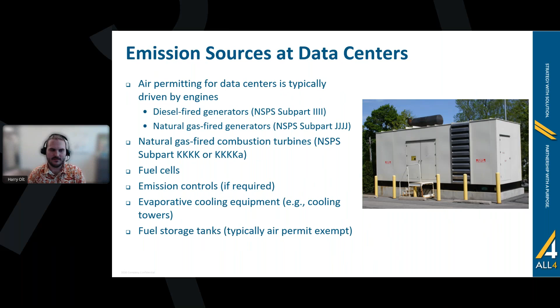Non-emergency generators and fuel cells are also considered for this on-site generation, and they would require air permits as well. If emissions controls are required for your site, those would also need to be in the air permit to take credit for emissions reductions. And those are the primary emission sources at data centers, but other equipment like storage tanks and evaporative cooling equipment could also be included in a data center's air permit.